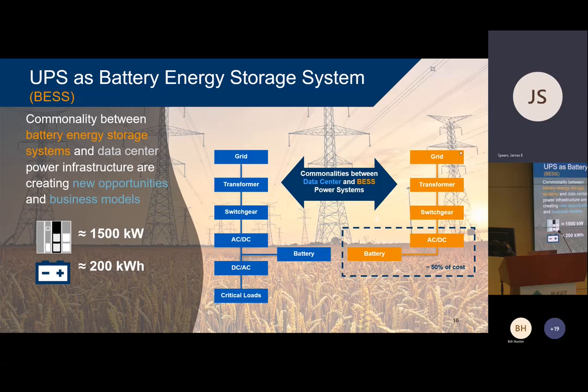If I'm considering a pure energy storage system, I have many of the same blocks: grid connection, transformer, switchgear, and a power converter—could be a bidirectional AC-to-DC, DC-to-AC converter—and a large battery that could easily be 50% of the cost. This isn't just a red-hot idea we had; customers came to us and asked, can we use our UPS as an energy storage system, or use our excess capacity to develop a revenue stream from the grid operator, or simply save money by shaving peaks and taking advantage of time-of-use electric rates?